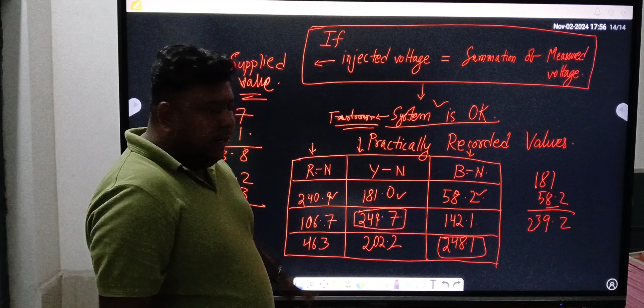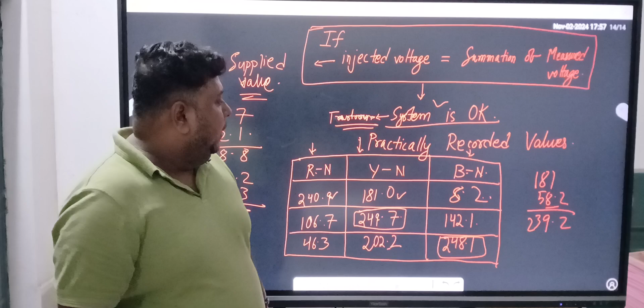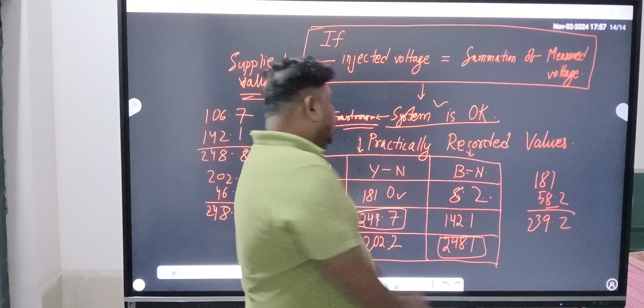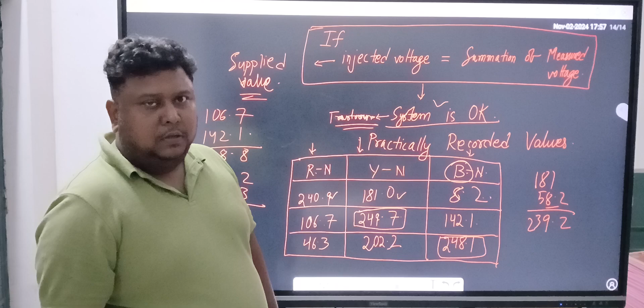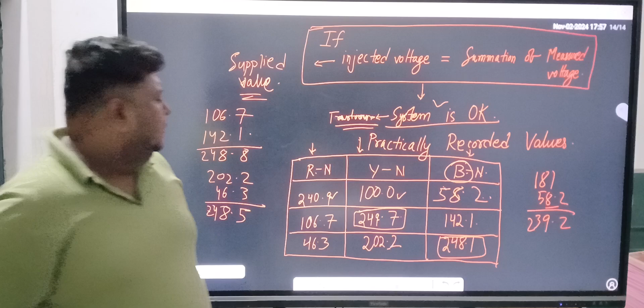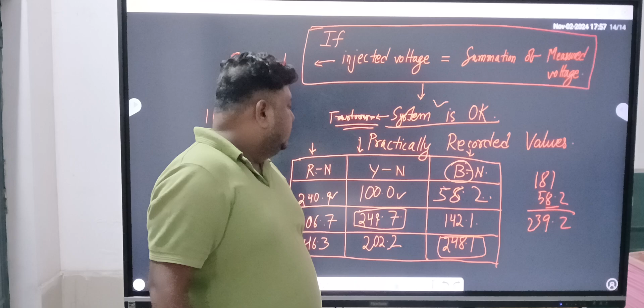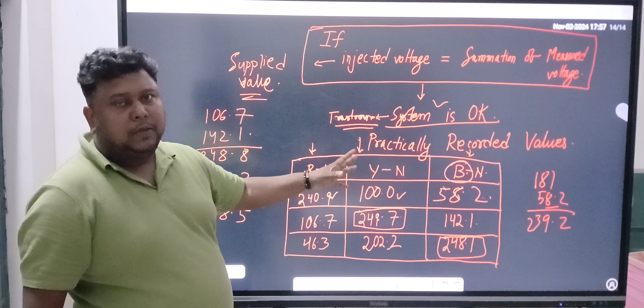Suppose we are not getting the value. Suppose for the measured value of 240.9, I have got 181.0, and here I am getting a voltage of 8.2. So here it can be concluded that this phase, the B phase, is having a fault. Is it clear? Suppose this was 58.2 as the previous value, but here, instead of 181, I am getting 100 or 101. So here I can conclude that the Y phase is having a fault. So this is the test condition. We can check whether the system is okay or which phase is having a fault. So this is all about the magnetic balance test.